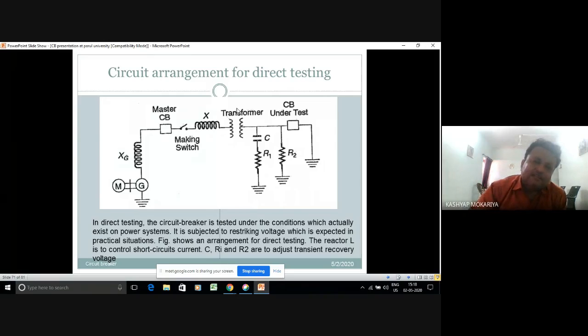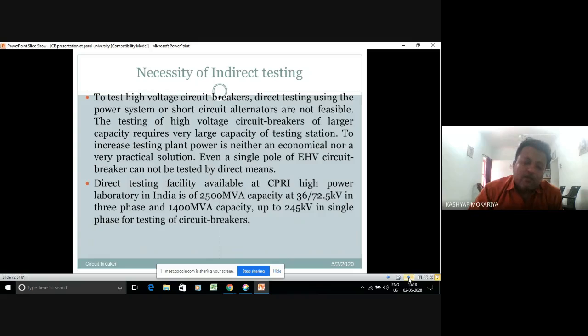The disadvantage is that you must have a big capacity alternator with a prime mover at your premises. That is a disadvantage of direct testing. So to test a high voltage circuit breaker, direct testing using the power system or short circuit alternators is not feasible. It should have a large capacity of stations. Direct testing facility available at CPRI, a high power laboratory in India, is 2500 MVA capacity at 72.5 kV in three phase, and 1400 MVA capacity up to 245 kV in single phase for testing of circuit breakers.